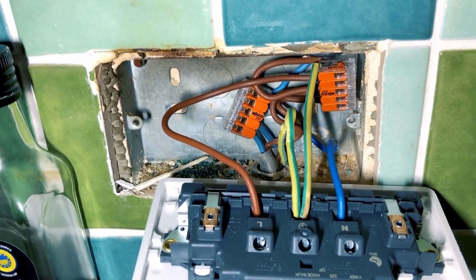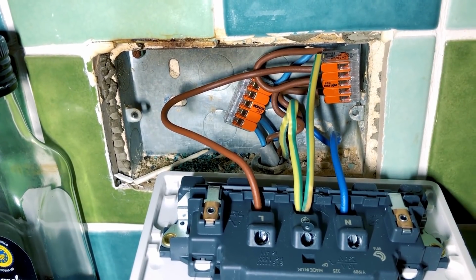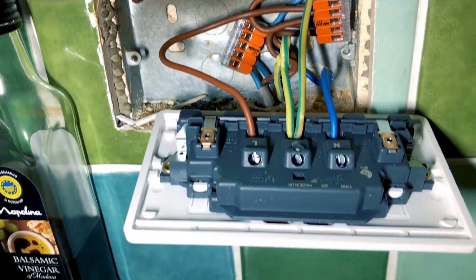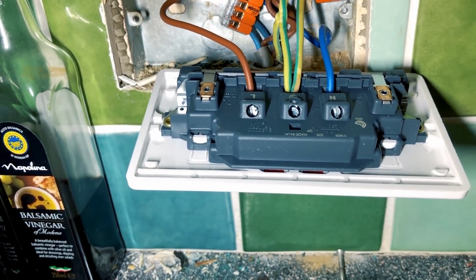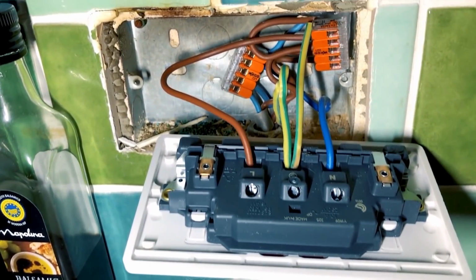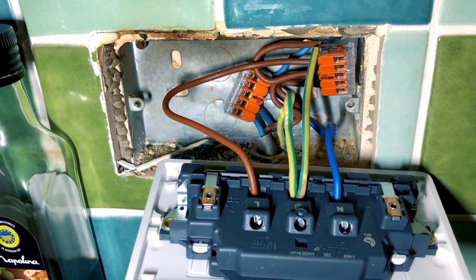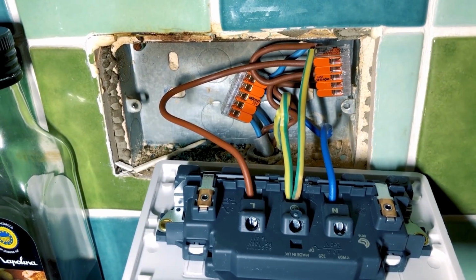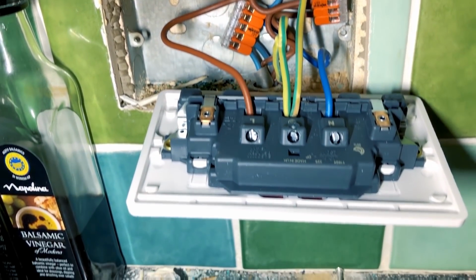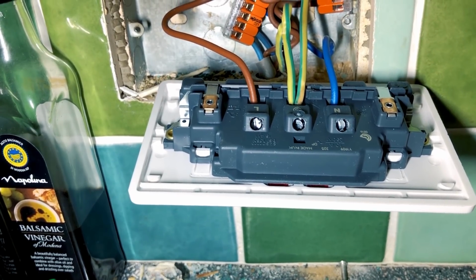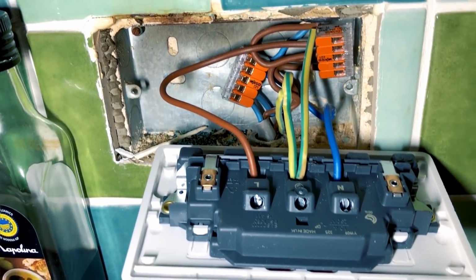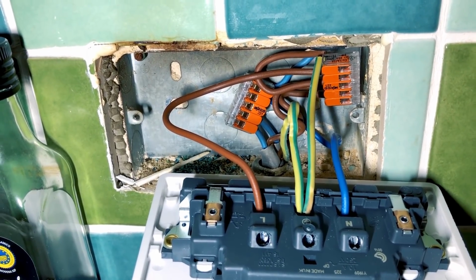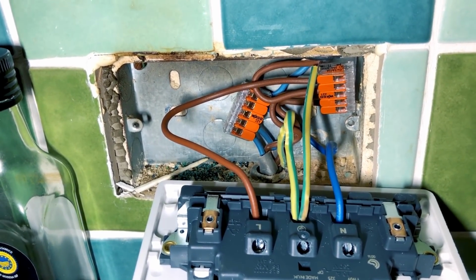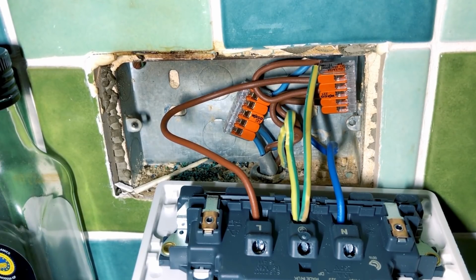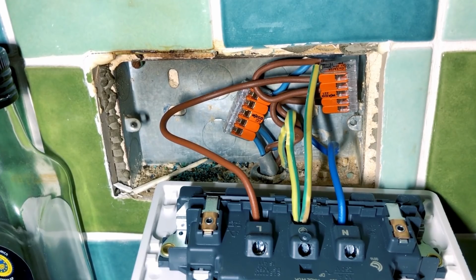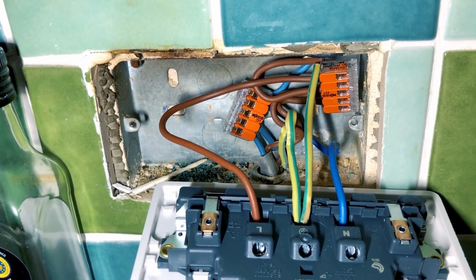So here we are, I've managed to cut out the burnt parts and just extend the good parts into the socket using these Wago 221 connectors. Thankfully the burnt part didn't extend all the way back into the sheath of the cables and into the wall. There was a bit of decent wire left, so I was able to salvage that and just extend them. It was a bit tight in the back of the socket, but it was doable, and much preferable for the customer than having to chop the tiles off and chase out the wall and do some kind of joint in the wall. So yeah, that was the solution that I came to in the end.